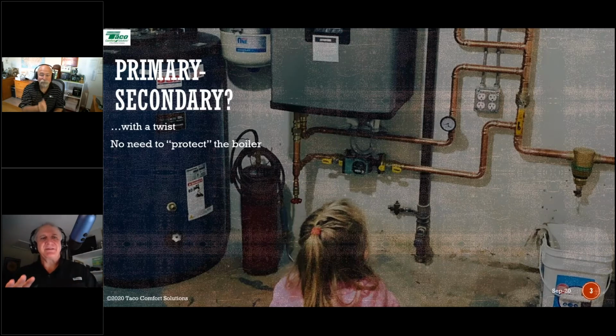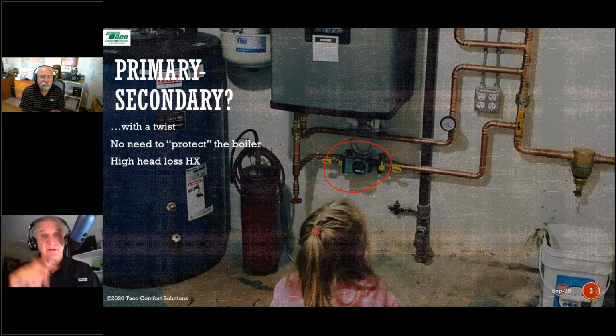So our piping arrangement is in no way designed to protect the boiler from low return water temperatures. It's to enhance the low return water temperatures, or encourage low return water temperatures to the boiler. Sure. It's also designed to make sure that we have adequate flow through what could be a high head loss heat exchanger, whether it's a stainless steel or a cast aluminum heat exchanger. They tend to be higher head loss heat exchangers. So this circulator becomes kind of critical. We want to make sure it's sized big enough without being too big, which again, is something we're going to talk about later on. So what we have here is our primary secondary with a twist.